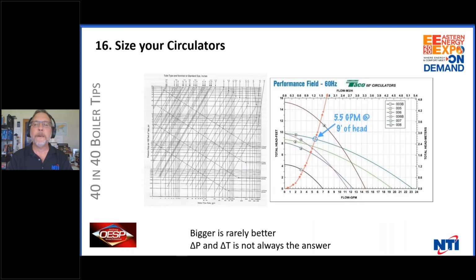Size your circulators. Yep, it's all about GPM and head. The day of putting in the hugest pump you can put in and turning it up as high as you can so you don't have a turn back is gone. Save your customer money on electric besides fuel. For God's sake, do your sizing for your circulators.